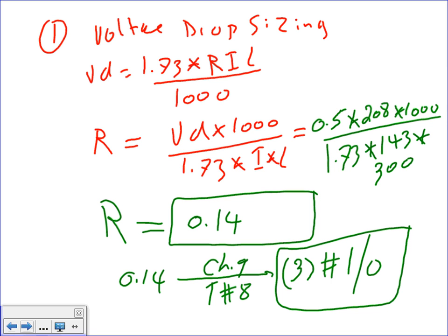Okay, so the first calculation gave us what? What did we get from the first calculation? 3 aught? So what does that mean? This one is already dropped because it's less than the first calculation. So I'm going to drop this calculation. Everybody knows why I dropped it? Because it gave me a conductor smaller than what I normally need to size the motor. So anybody know why we came up with a small conductor here? Because when we size the continuous load, we add 25% extra amps. That's a lot of amps.